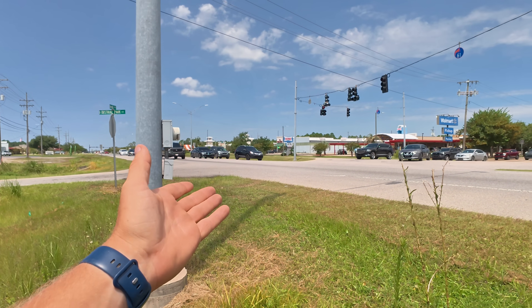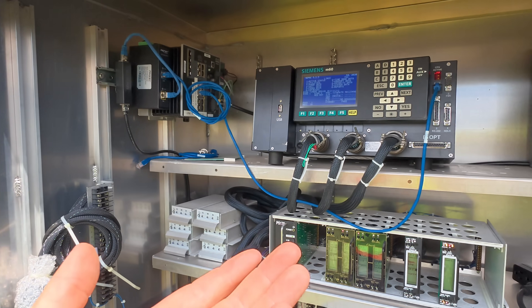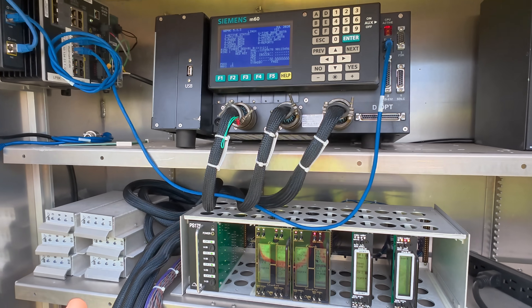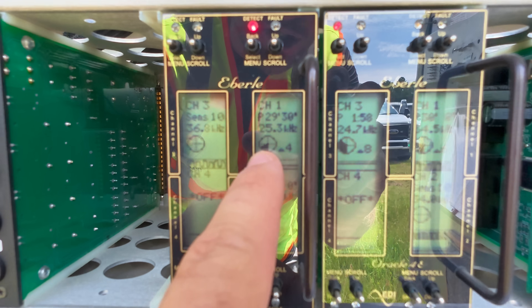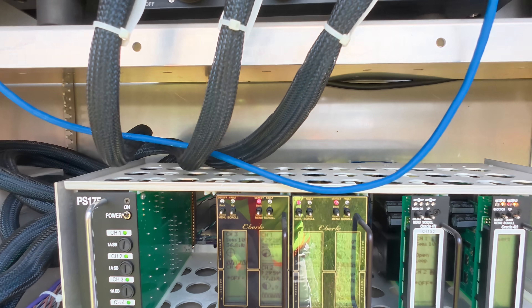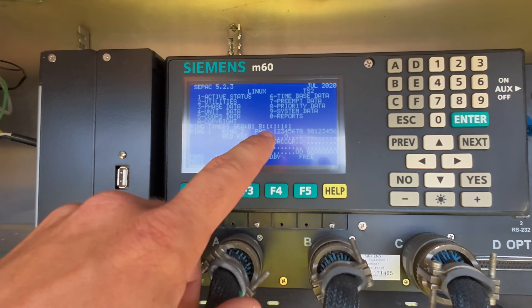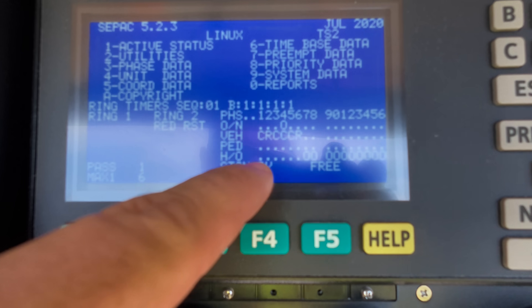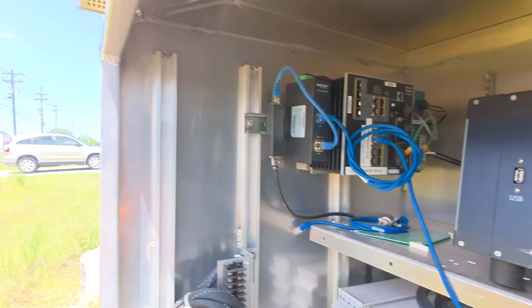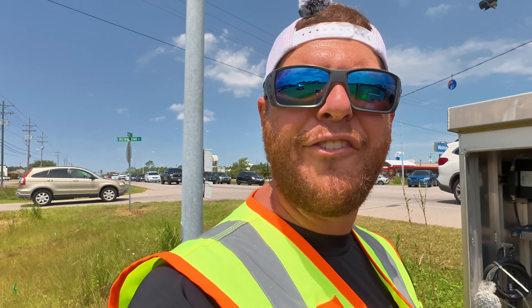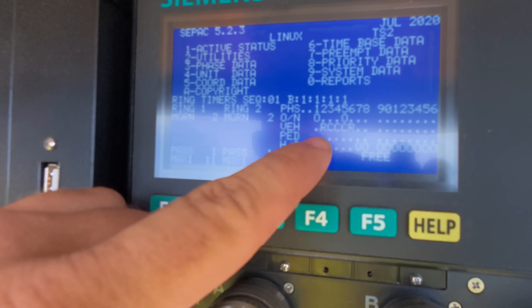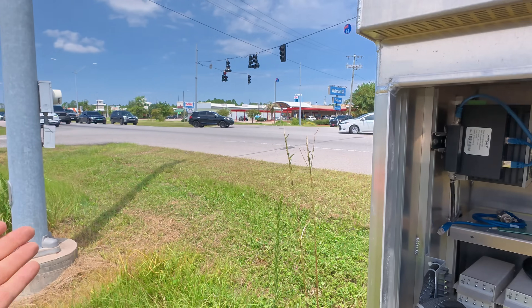As you can see, these vehicles in this left turn — that is approach phase one — and you can see how it is picking up the disruption in the electromagnetic field, which is then putting in a call to this traffic signal controller cabinet. With the 'N' over it, it is going to be going to phase one and phase five next, which is the left turn lanes.